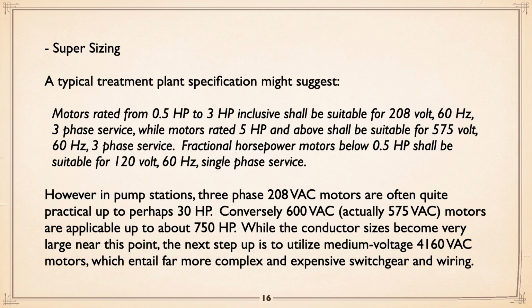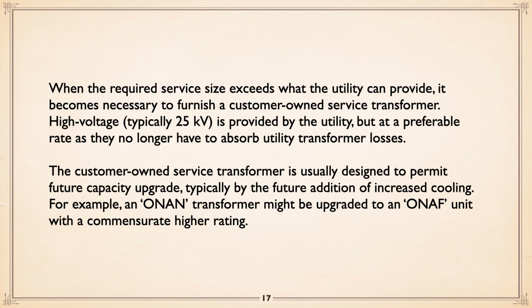I'm glad we did. Now, when the required service size exceeds what the utility provides, in other words, if they simply haven't got transformers big enough to feed your water treatment plant or whatever, a big pump station, then you end up providing the transformer, or the client does, a customer-owned service transformer. High voltage, up to say a typical 25 kV, 25,000 volt, is provided by the utility, but at a preferable rate. It's a little cheaper buying power from them that way. Why doesn't everybody do it? Because normally they are absorbing the transformer loss, where this way you're absorbing the transformer loss.